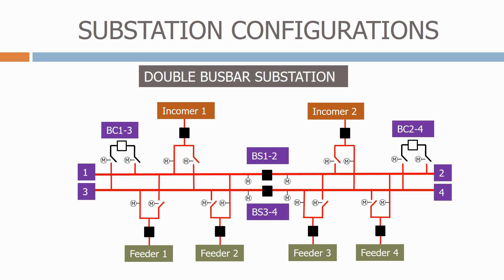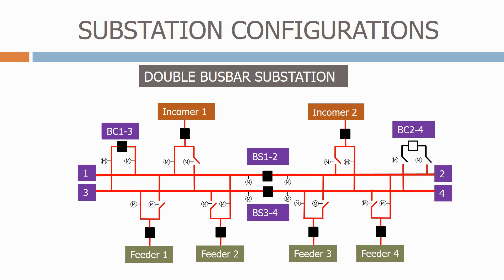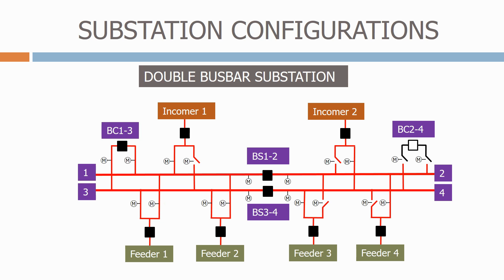Let's see how we achieve the on-load changeover. Firstly we close one of the bus couplers to connect the two bus bars together. The bus coupler has an inbuilt synchronising relay to make sure that the parameters on each bus bar are the same. Once the bus coupler is closed we can close the second bus bar isolator on each of the feeders. Once this is done we can open the original bus bar isolator, and we've now changed over which bus bars the feeders are connected to. We then open the bus coupler circuit breaker again, splitting the bus bars.